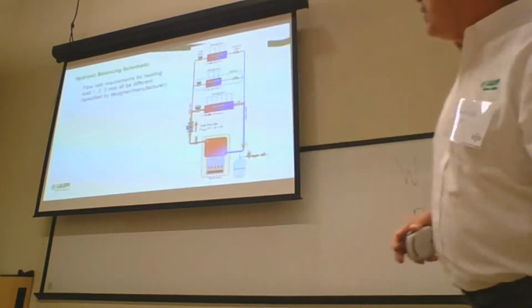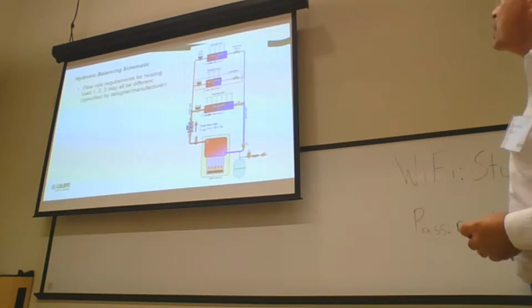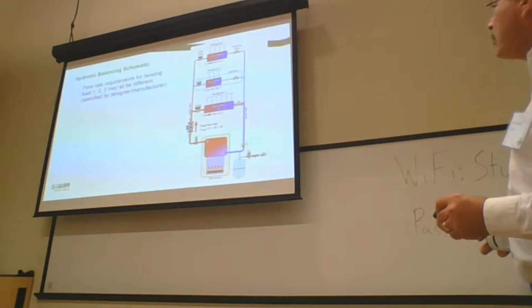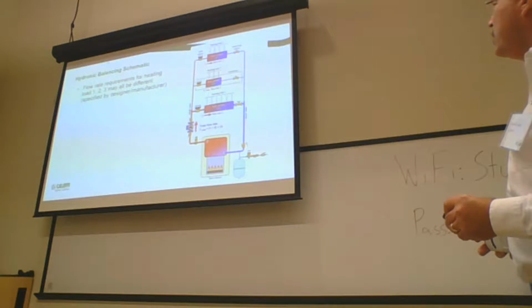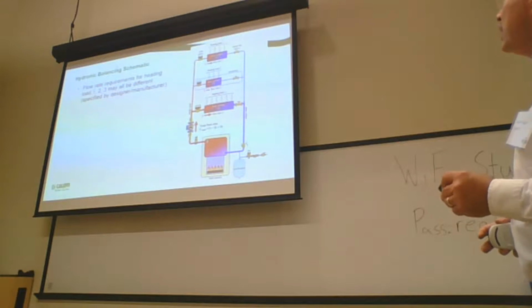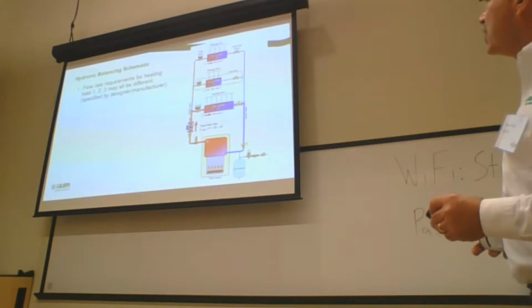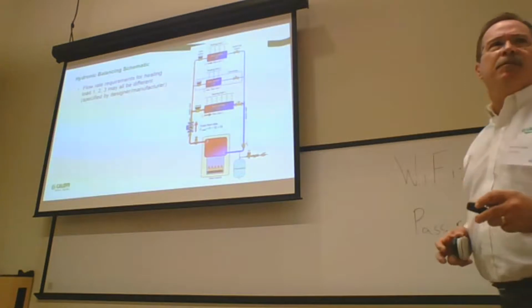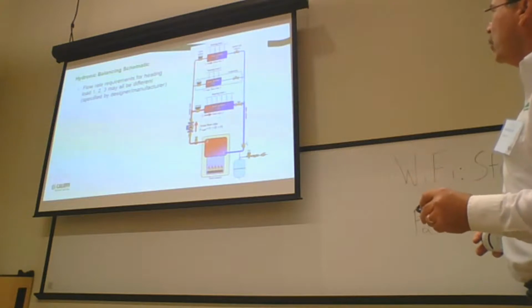We're going to start with a really simplified hydronic balancing schematic here. Now this will look a little familiar. Luciano covered some of this morning. But let's say you have a residential boiler. This might be in your home. So we have a fill valve here that provides water to the system, an expansion tank. This is a closed system, and this boiler will produce hot water for these heat emitters. This device here is an air separator, because air in hydronic systems is bad, causes corrosion and all kinds of really bad stuff. So if you ever see this symbol here, that's an air separator.